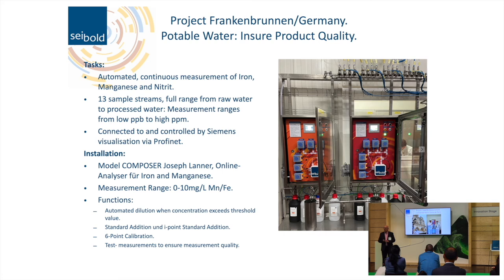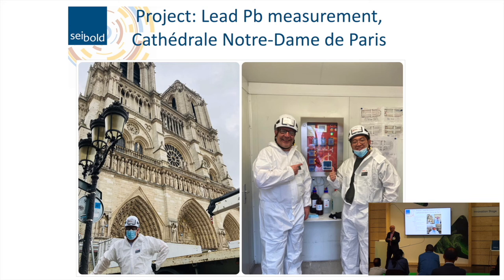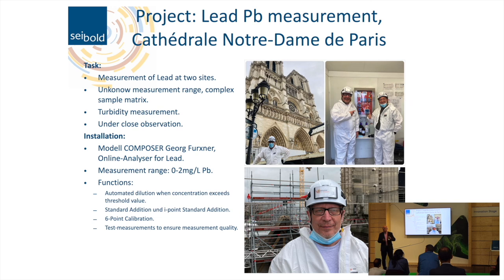Another nice example is the Notre Dame Cathedral. You remember 2019 — 400 tons of lead roof were burned and fell down into the cathedral. Lead contamination was everywhere — on the ground, and everything you touch may be contaminated. We have two stations at two outlets monitoring the contamination. We also measured turbidity to correlate it with lead concentration. The basic idea is to measure whether there is contamination, how significant it is, and to track this after lead treatment — with automatic dilution and daily test measurements.